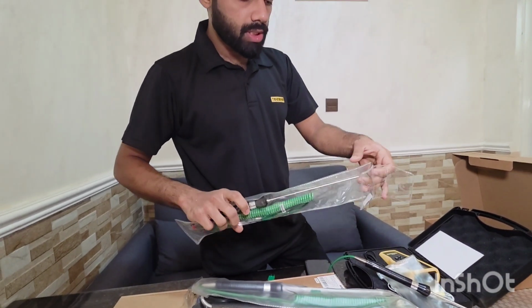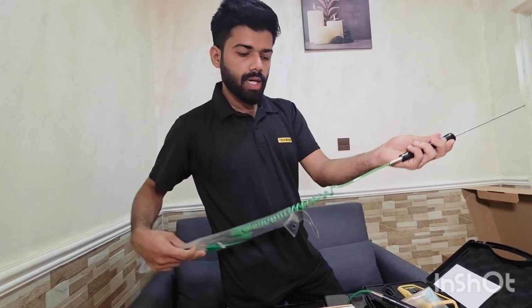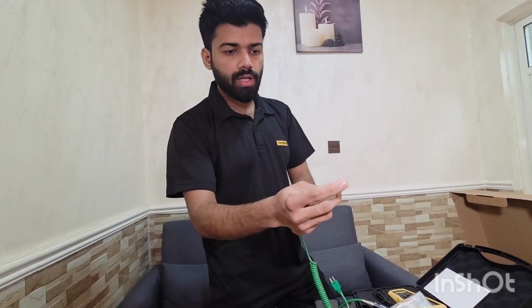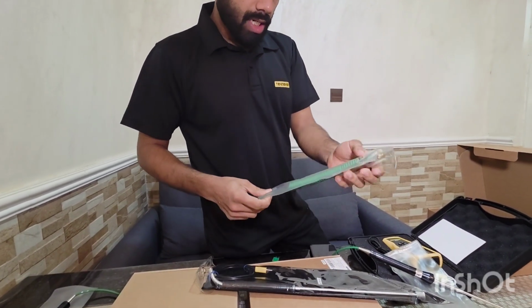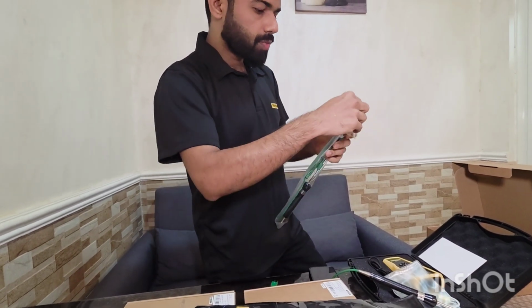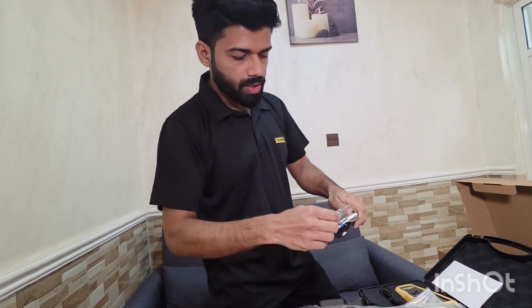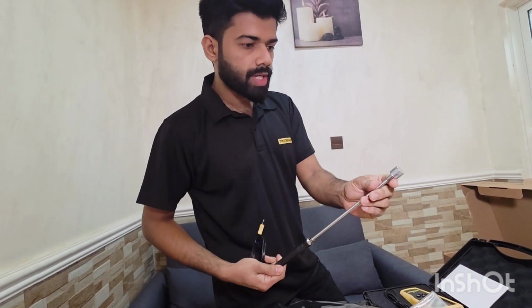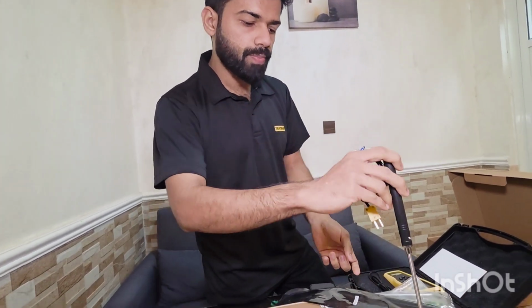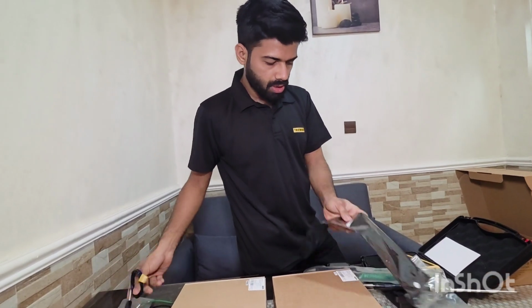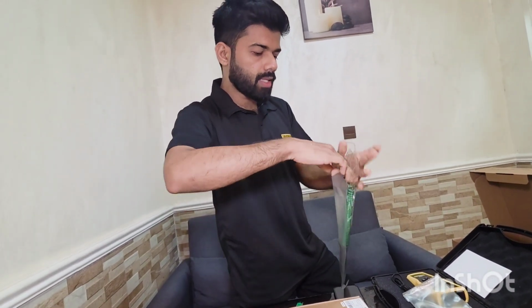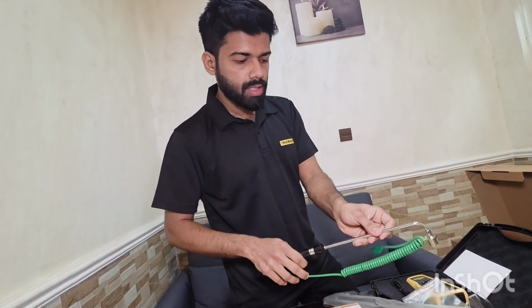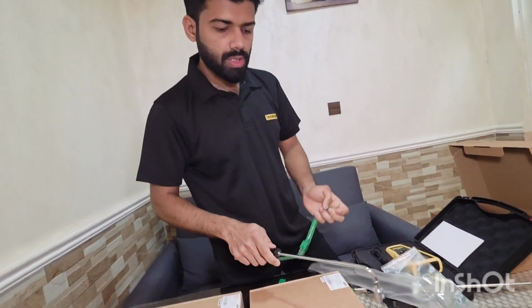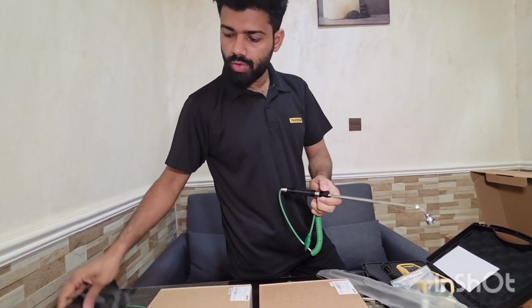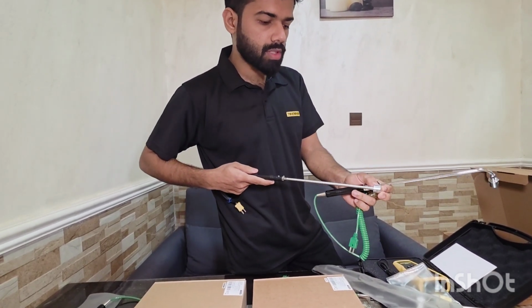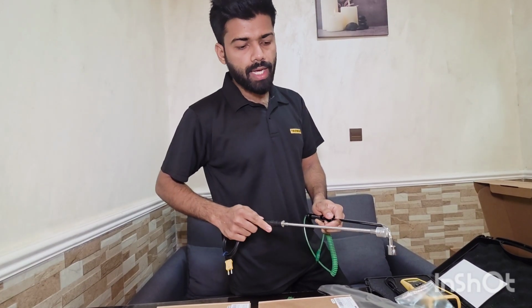And there is another probe which is an immersion probe. You can use it to immerse in liquids. This is an immersion probe without a pointed tip. Then next I took two surface probes. Surface probes are used to measure the surface temperature. So this is a straight surface probe, and you can measure the surface temperature using it. And there is another surface probe I took, which has an angle-shaped head at the tip. For areas where you cannot use a straight surface probe, you can use this angular type for convenience.